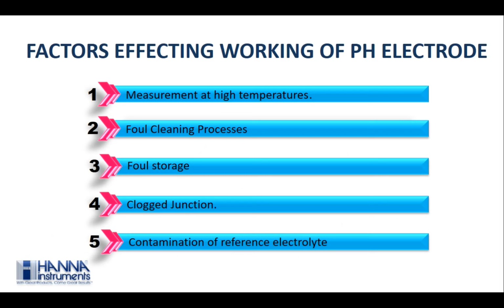Then, the cleaning process. The most common cause of inaccurate measurement is a dirty or improperly cleaned electrode. Remember, just because an electrode looks clean does not mean it is. This is important because during calibration, the instrument assumes that the electrode is clean.